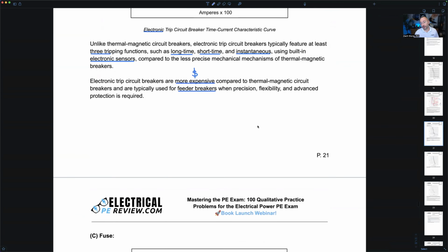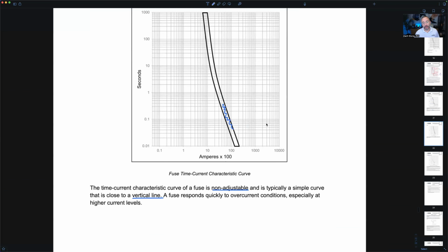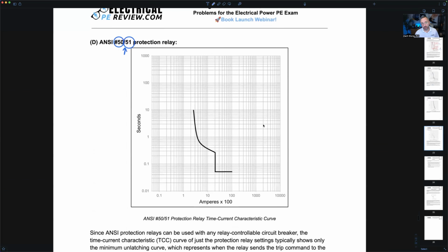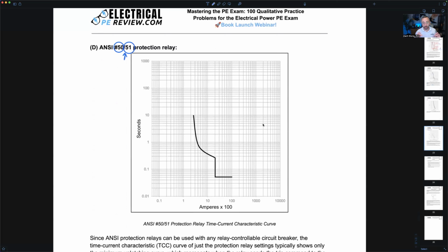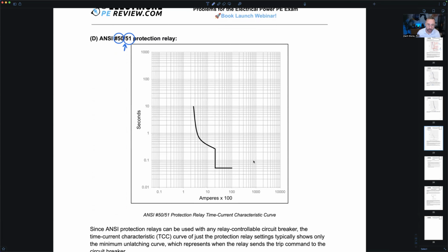Relay sits there monitoring its input signals, typically from a current transformer for current tripping for overcurrent. And then it says, hey, boom, there's a fault, there's an overcurrent condition, there's an abnormal condition, your turn. It's like tag, you're it. And then the breaker is going to operate. But so here we have a 50/51 protection relay. This would be our instantaneous trip. And this would be our ANSI 51 overcurrent, time delay, time overcurrent trip.